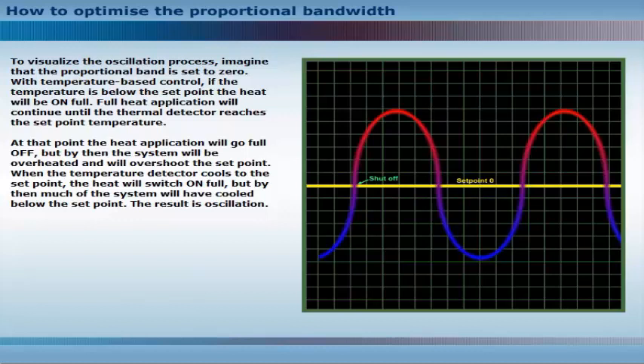When the temperature detector cools to the set point, the heat will switch on full. But by then, much of the system will have cooled below the set point. The result is oscillation.